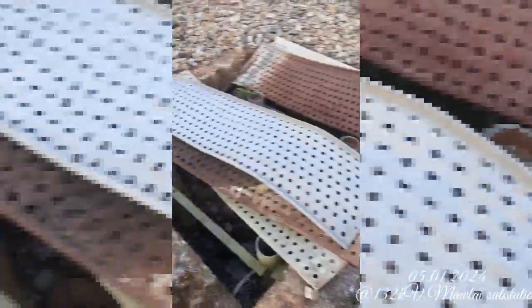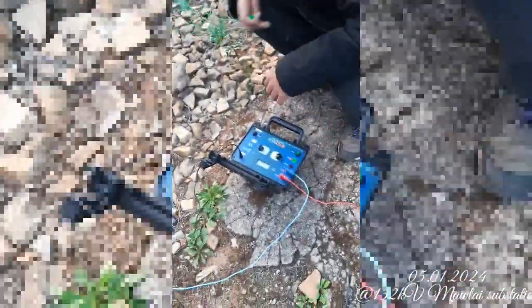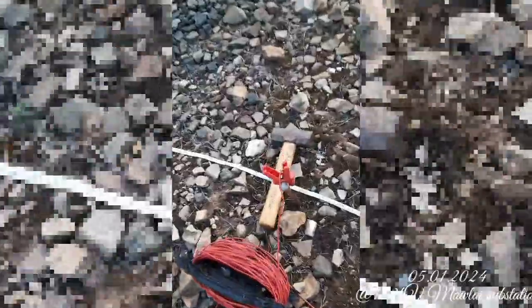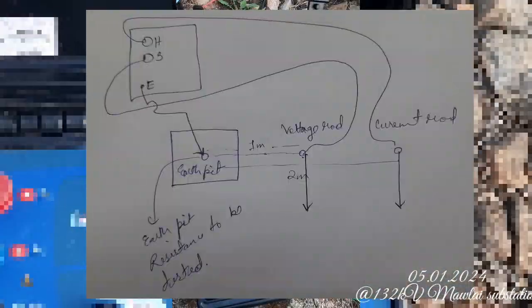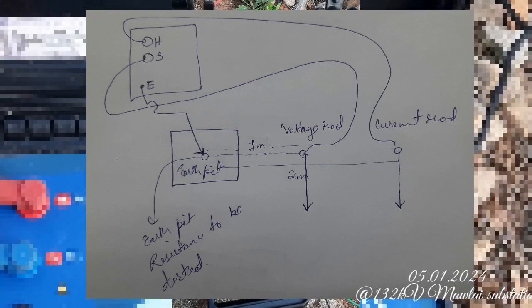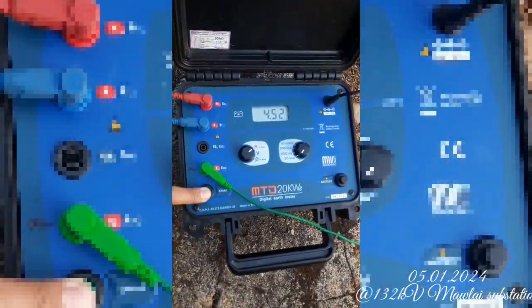For each earth pit, you have to take 4 readings: one for the east direction with the voltage rod at 1 meter and current rod at 2 meters, connected as shown, and you take the reading. You do the same for west, north, and south directions. So for each earth pit you get 4 readings, and then you just take the average. You have to do this for other pits also, since every substation has multiple earth pits.